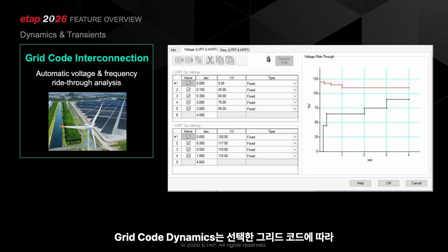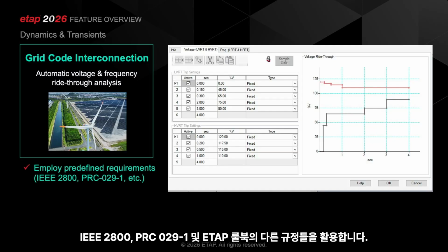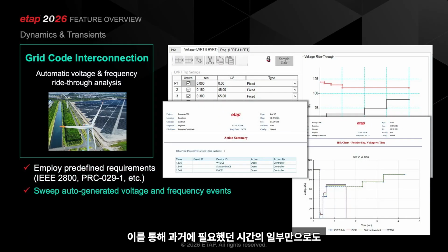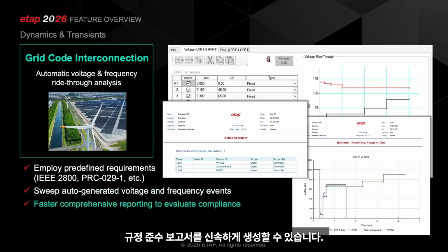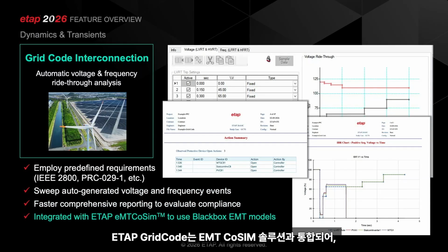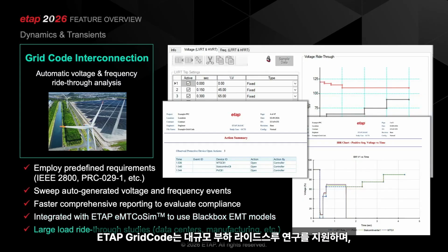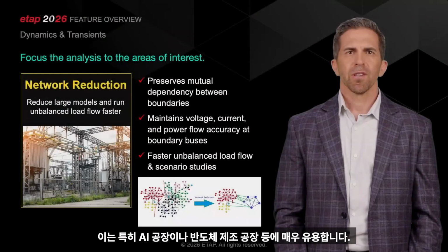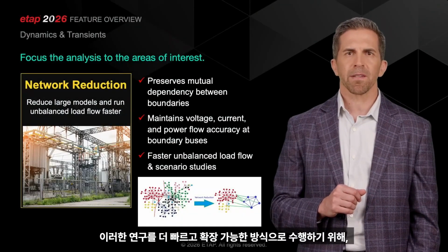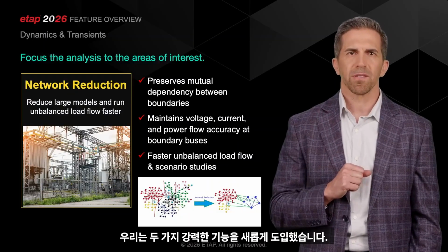Grid code dynamics automatically generates voltage and frequency ride-through events based on your selected grid code, IEEE 2800, PRC 029-1, and others from the ETAP rulebook, sweeps them to produce a compliance report in a fraction of the time it previously required. ETAP grid code integrates with our EMT CoSIM solution, which allows users to use black box EMT models while performing interconnection studies. ETAP grid code supports large load ride-through studies, which is especially useful for AI factories and semiconductor fabrication plants. To conduct these studies in a faster and more scalable manner, we have introduced two powerful capabilities.